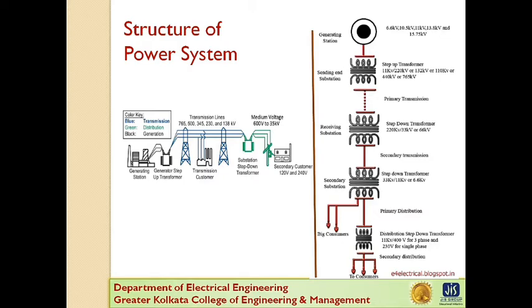For economy in the transmission of electric power, the generation voltage, that is 11 kV, is stepped up to 132 kV at the generating station with the help of a three-phase transformer. It may appear advisable to use the highest possible voltage for transmission of electric power to save conductor material and for other advantages. But there is a limit to which this voltage can be used. This is because an increase in transmission voltage induces insulation problems, and the cost of the switchgear and transformer equipment is increased. Therefore the choice of proper transmission voltage is essentially a question of economics. Generally, the primary transmission is carried out at 110 kV, 132 kV, 220 kV, 440 kV or 765 kV.